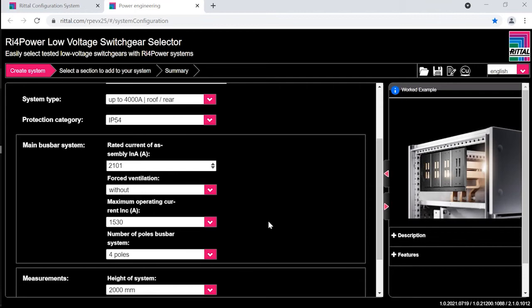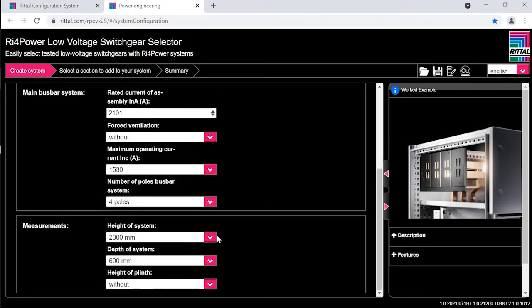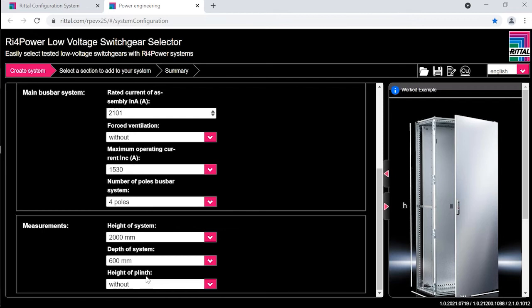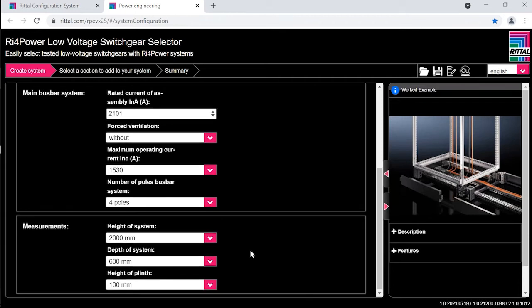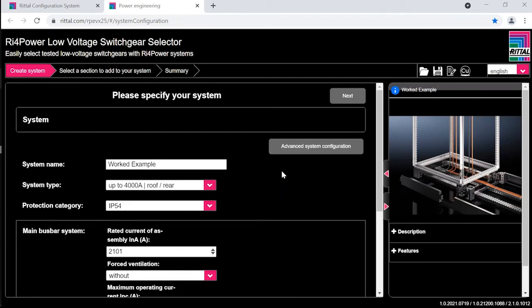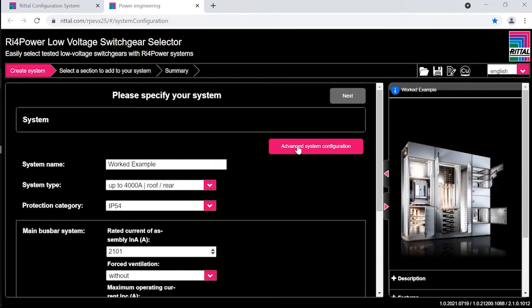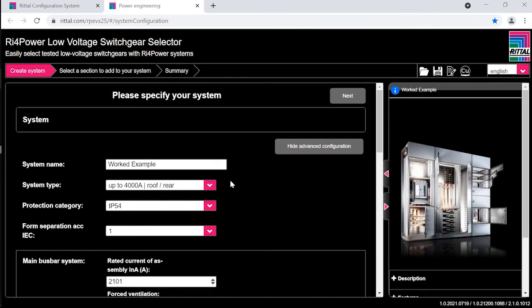It is a 4-pole system, and here we can select the basic layout of the panel. So 2 meters high, 600 deep. We have an option for 800 deep, but we'll go with 600, and a plinth at the bottom, which will be a 100 millimeter high plinth. So that is the basic information. For the most advanced system, it will drill down into the first page of selection.